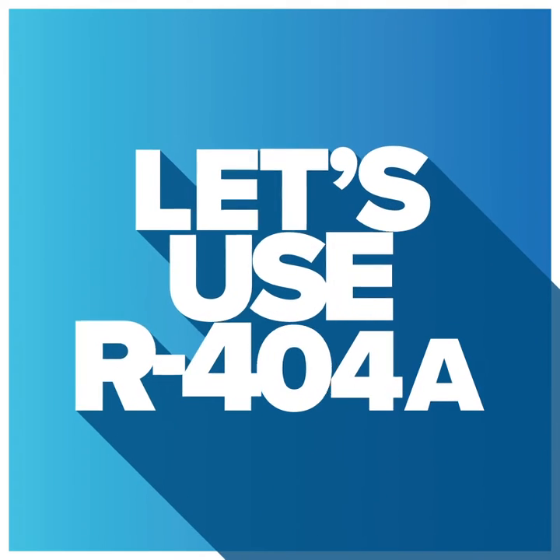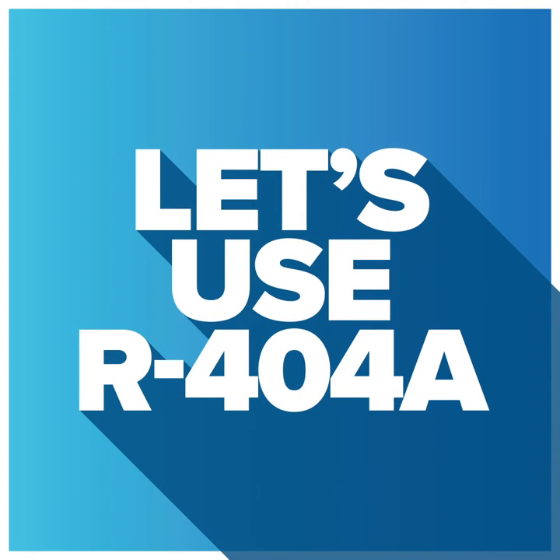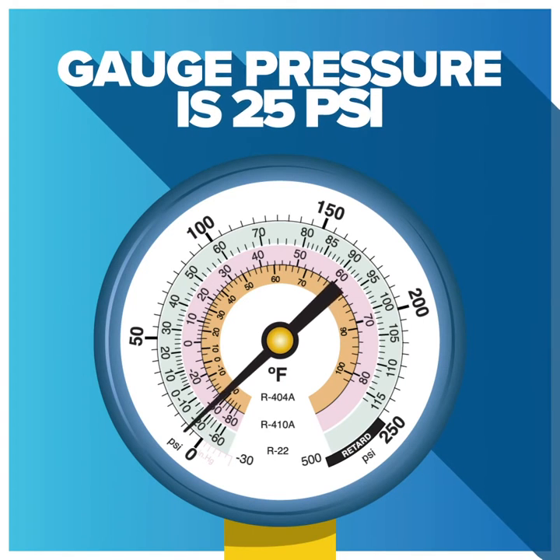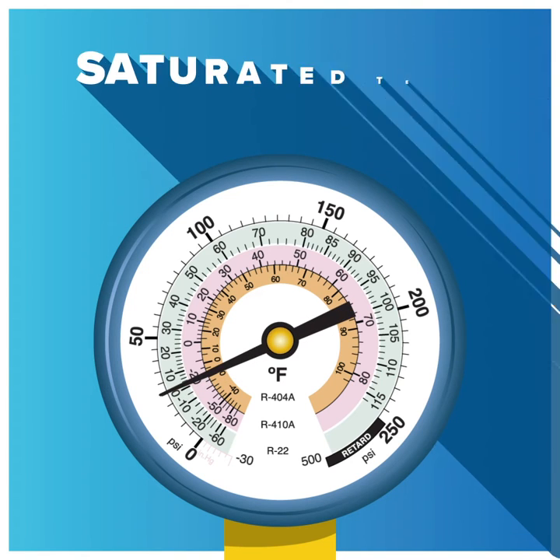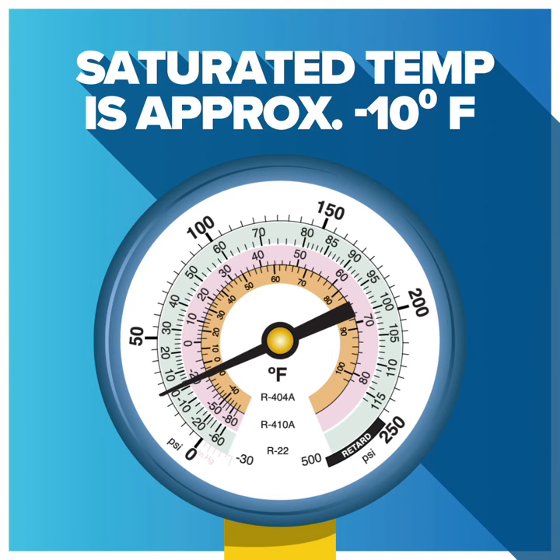Let's use R404A to demonstrate how this feature works. The gauge pressure shown here is 25 psi. The corresponding saturated temperature would be approximately minus 10 degrees Fahrenheit.